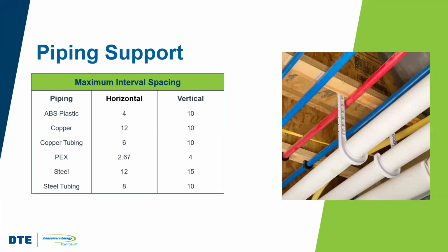And in addition to the piping being supported, for baseboard convectors in particular, we want to make sure that they are supported, and that's independent of the pipe, right? So here we can see that pipes are supported. We've got supports that are suspended from joists, and we want to make sure when we've got those baseboard convectors that those are supported independent of the piping, right? So that means attached to the wall or something there.